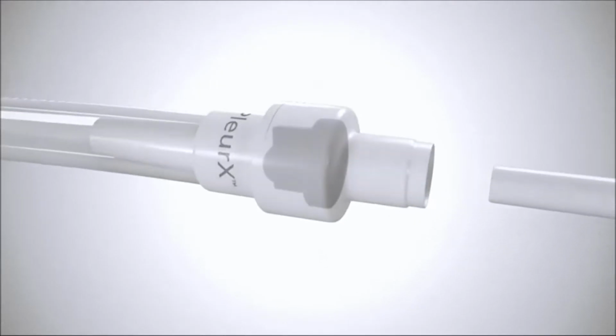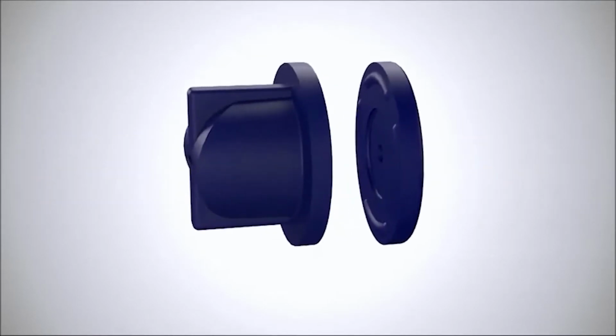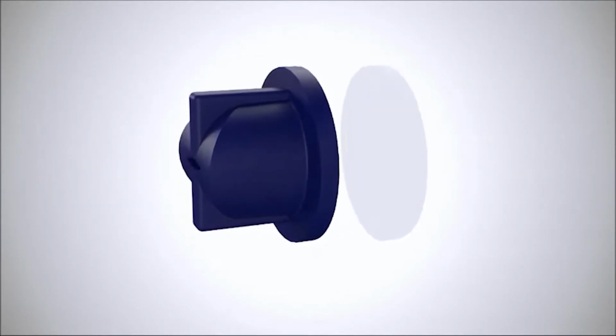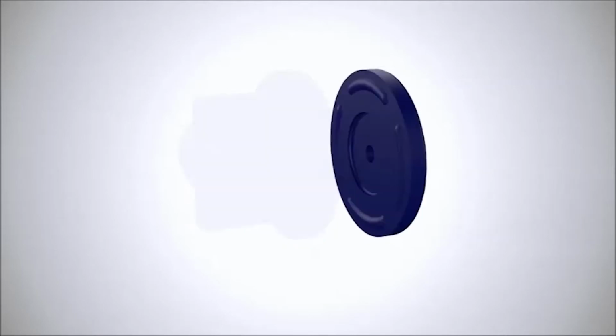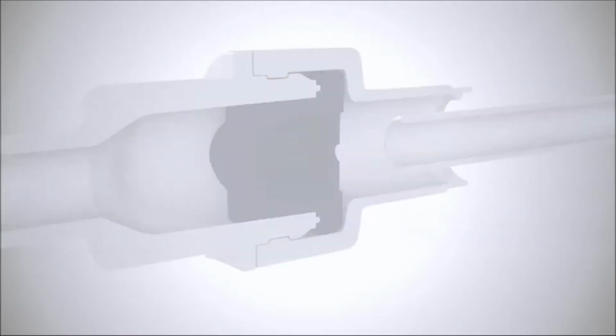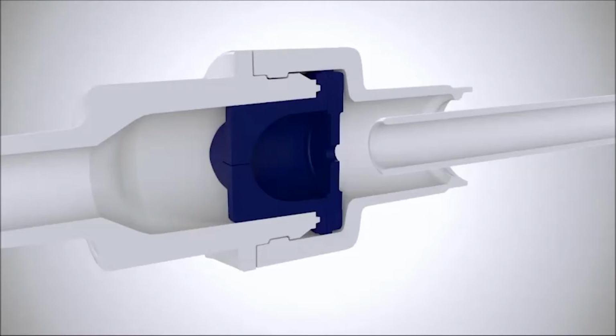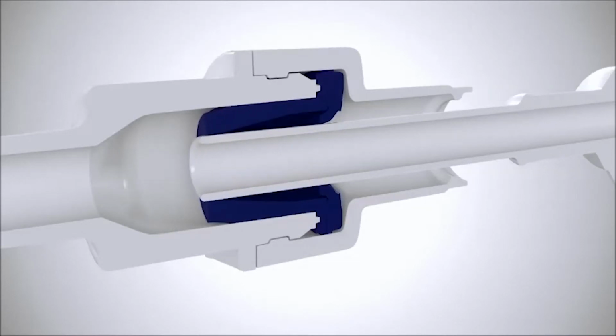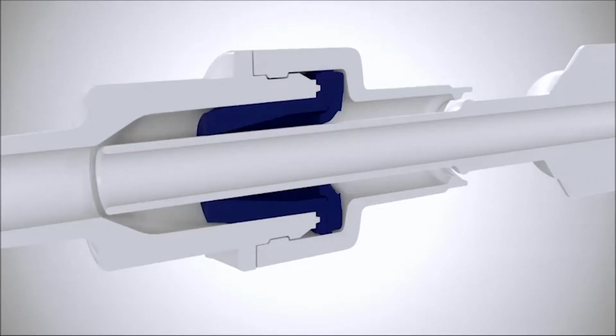The primary valve keeps the catheter closed when the patient is not draining. The secondary valve provides a backup seal around the access tip when the patient is draining. When the valve and access tip mate, the primary and secondary valves are forced open. When mated, the access tip creates a channel through the entire valve, allowing any debris in the patient's fluid to flow directly into the drainage tube without clogging or getting caught in the valve.